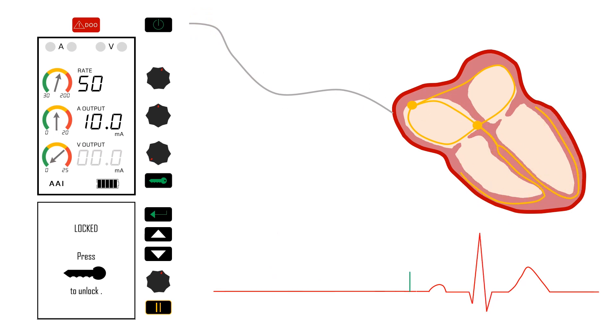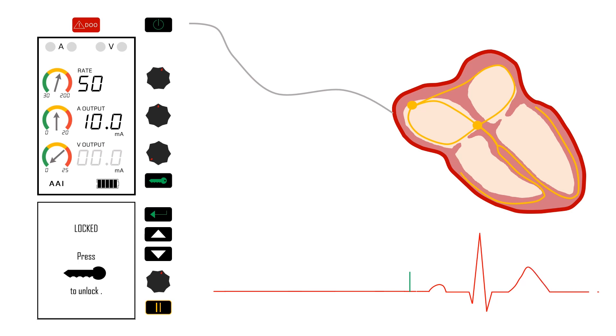Now the heart has no intrinsic atrial activity. Therefore, nothing is sensed by the pulse generator, and pacing is no longer inhibited. The pulse generator will now pace the atria at a set rate. The set rate determines how long the pulse generator waits while listening or sensing before generating a pacing impulse.